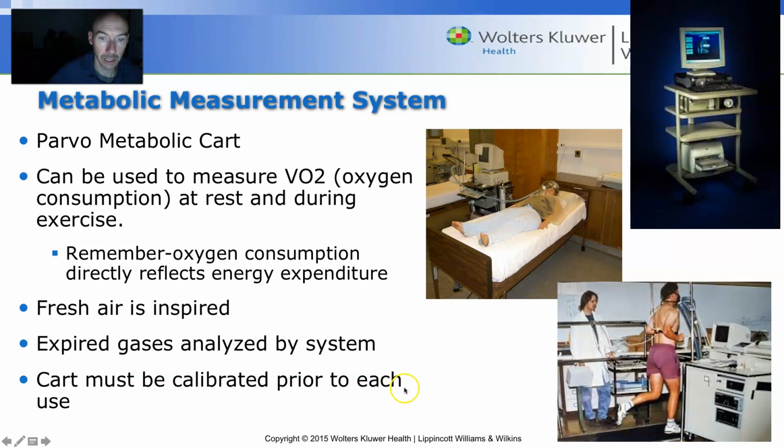Cart calibration, as I mentioned, we do that prior to every test to account for the changes in barometric pressure, air temperature, and relative humidity. Where I live in the city of Louisville, Kentucky, the humidity and the barometric pressure change pretty frequently because we're in a valley. So as weather comes in and out, those variables change a lot. Where you all are up in Ohio, it's probably not quite as drastic, but still it's going to change, you know, minimally every single day. So you want to make sure you calibrate it before every use.